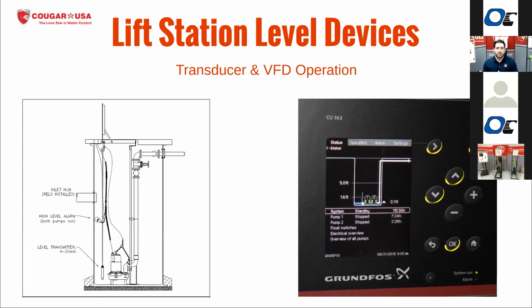And eventually, when it fails, it's going to send a 0 reading to the controller, meaning it's not going to register any water being in the pit. So no matter what happens in the actual pit itself, the pumps aren't going to turn on. So we always pair that with a backup float switch here.